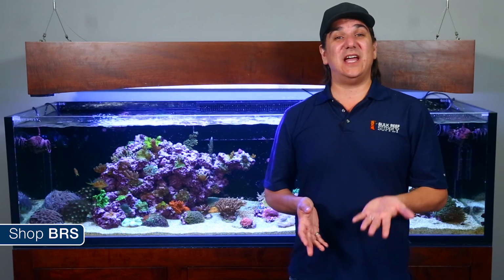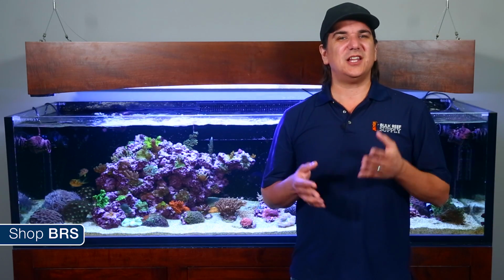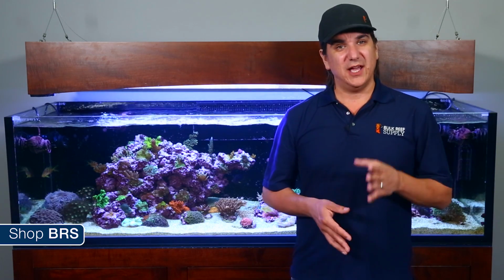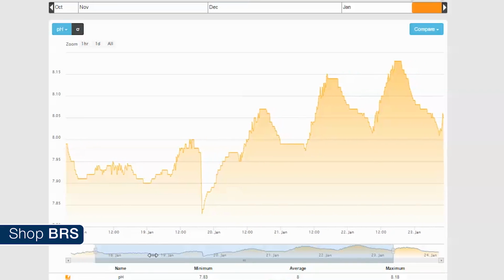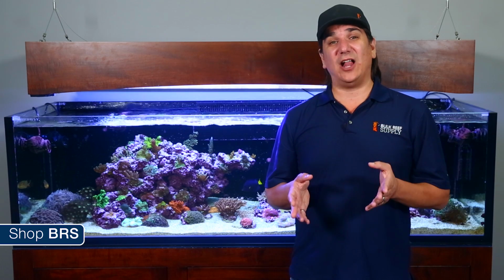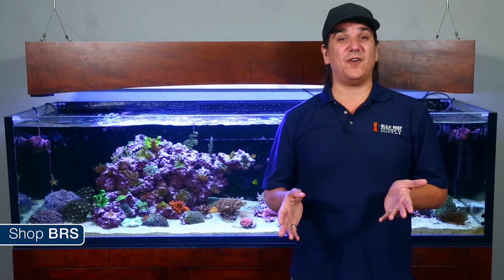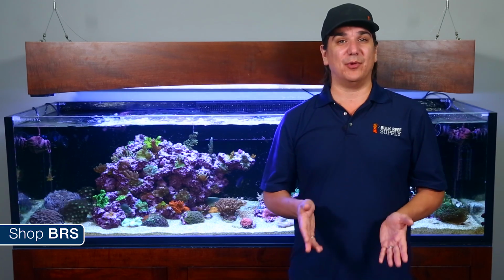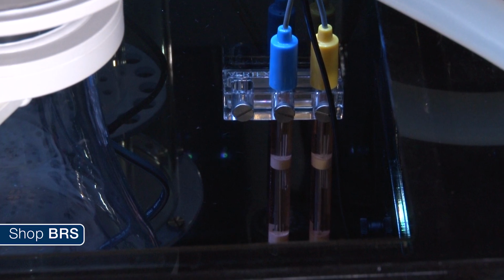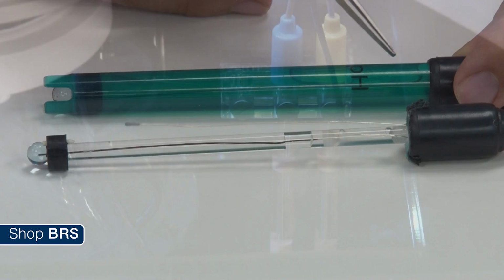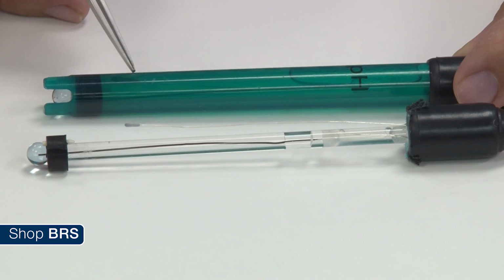The third is using pH for simple alerts or alarms to let you know when something major is going wrong. In this case, I would certainly monitor it from time to time, but you likely will need to calibrate it every 6 months to make sure it hasn't fallen significantly outside of its operating range. Now, all this assumes you're using a decent probe to begin with. Probes with poor quality seals and junctions will need a bit more attention.